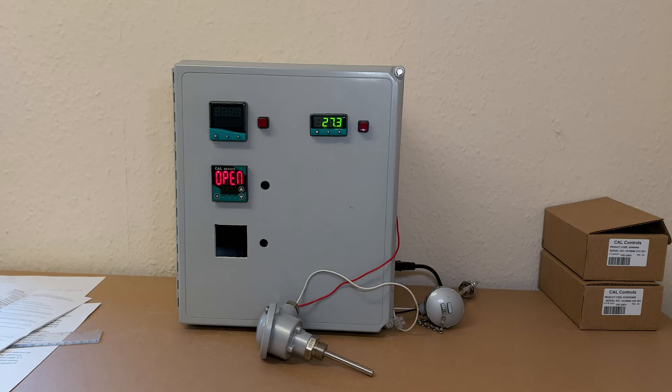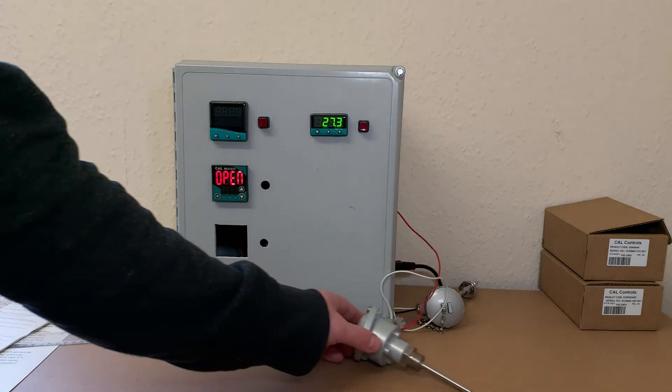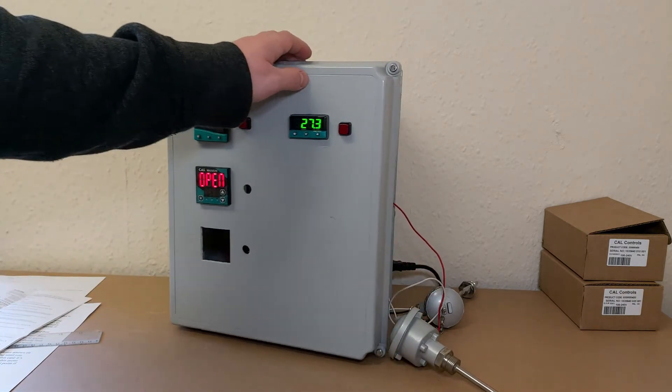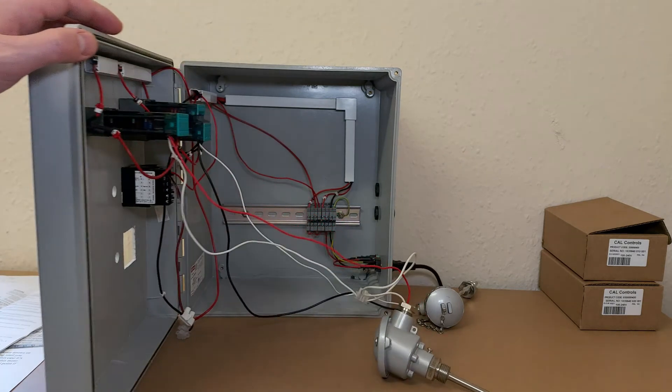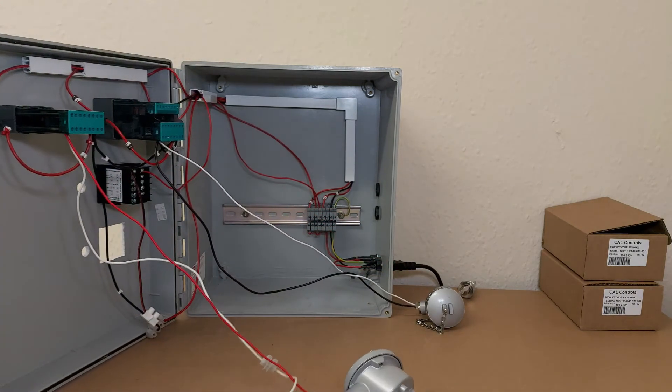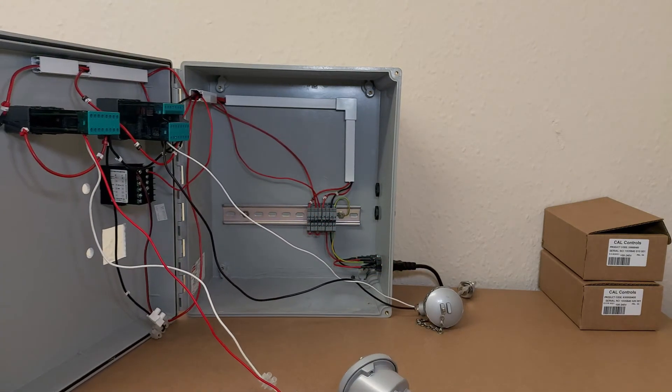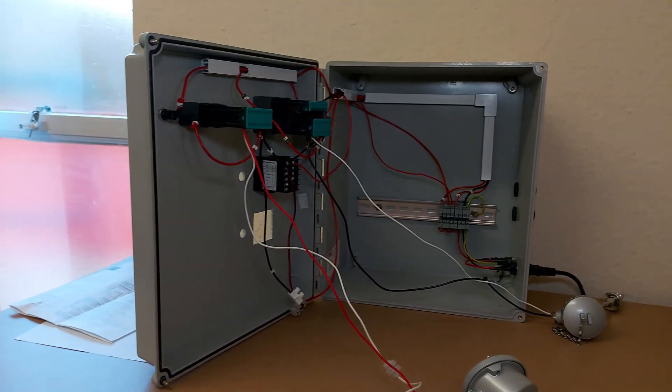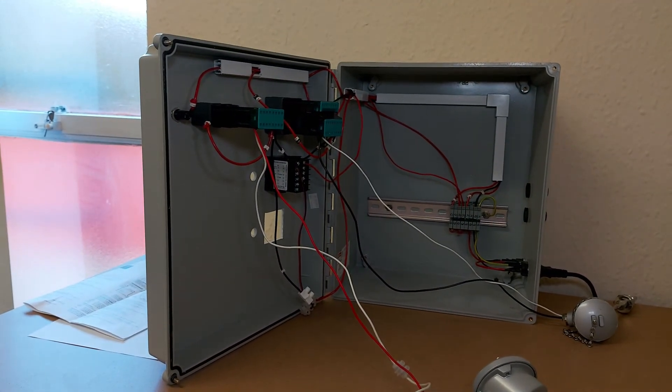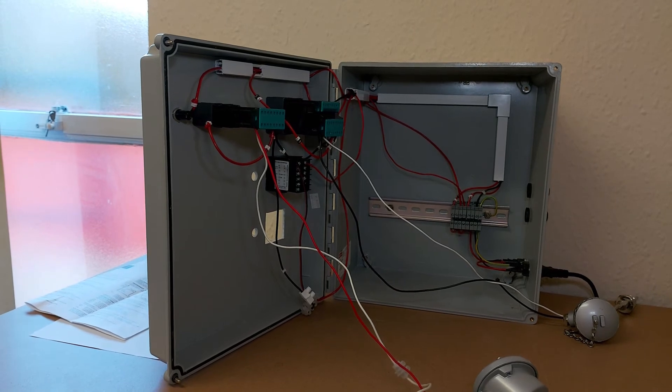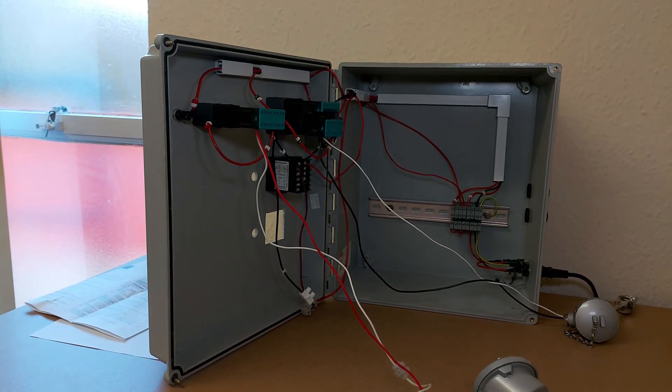On the controller, there are two terminals for the PT100 input. The wires from the temperature sensor will usually be red and white, which is the industry standard. It does not matter which way around they are connected.